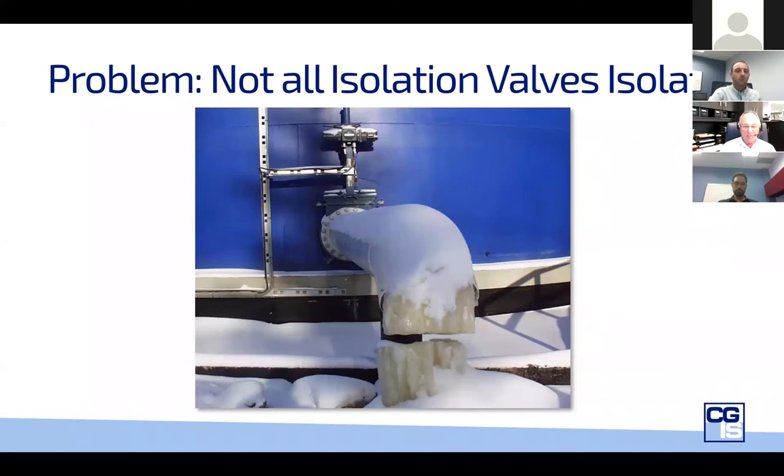The problem was trying to describe what was needed with tools that weren't completely developed. When we looked at the data sheet, we made an error. We bid a valve that was designed to not do that, but we didn't get the order because we didn't bid what they asked for. This was an MSS SP-81 knife gate valve made by a proper manufacturer — not a bad valve, just the wrong valve for this application for seven months of the year. In the summertime when it was above zero, the leakage could be accepted.